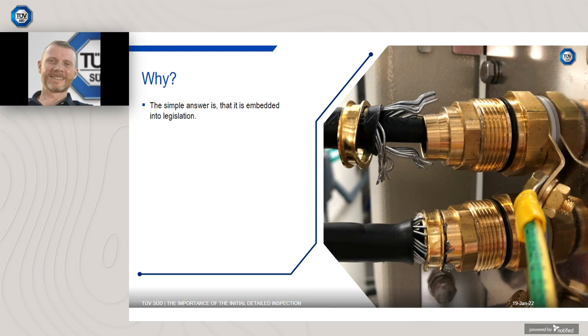Why do we inspect? The simple answer is that it's embedded into legislation. The requirement to maintain plant and equipment in good working order is detailed in a number of legislations and directives. Inspection and maintenance is the best way to ensure the integrity of plant and equipment. The point of the legislation and regulations and directives shown below is to allow the use of electricity in potentially explosive atmospheres. Not all are listed, for example, the offshore installation cases. A point often overlooked is that inspection before first use or delivery, as well as looking for safety issues, can also save money and reputation. The photo in this slide is a general photograph showing some poor glanding. In this instance, the supplier had to fix this and many other issues at his own cost.